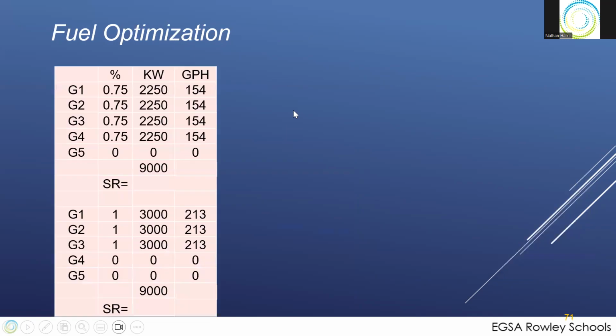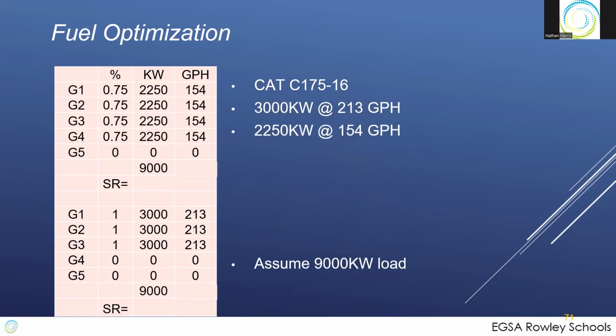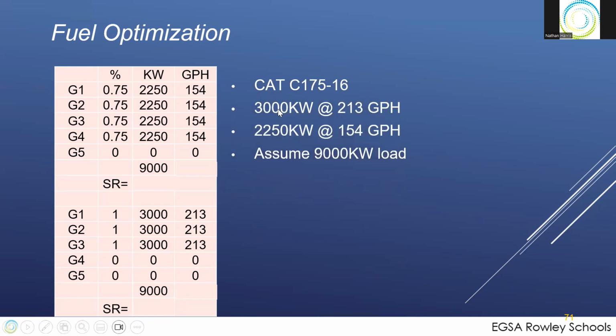Let's take this one step further, and these are obviously made up numbers, well, based on true numbers, okay? Again, we're picking on the 175/16. At 3,000 kW, it burns 213 an hour. At 2,250, it burns 154 an hour. If we assume a 9,000 kW load, and this is where I'm taking a little liberty with the calculations, it just makes it so pretty when you look at it.